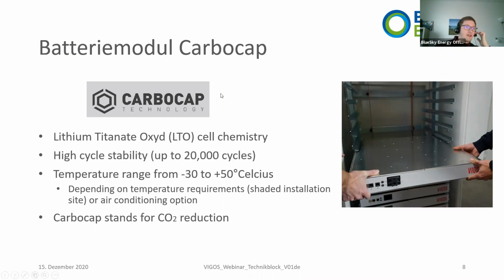So as already said, this module, which you can also see here in the picture, is made out of 22 lithium titanate oxide cells. So 22 cells, which give us 40 amp hours of capacity and around 2.0 kilowatt hours of storable energy. The cell is really a long life cycle battery. So it has high cycle stability up to 20,000 cycles. And here in the cycles, we mean full cycles. So really use 100% out of the cell.